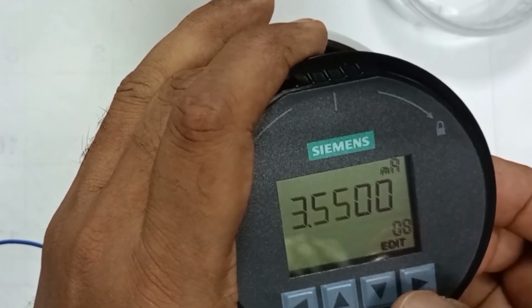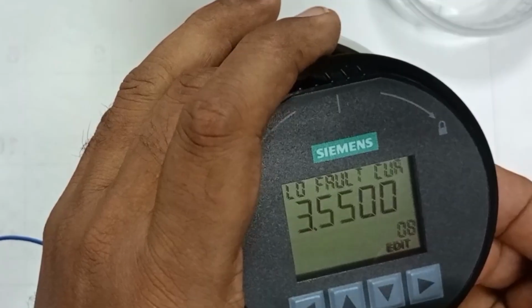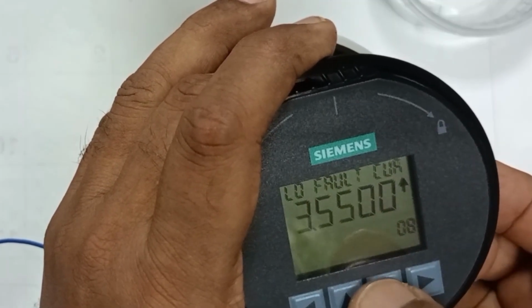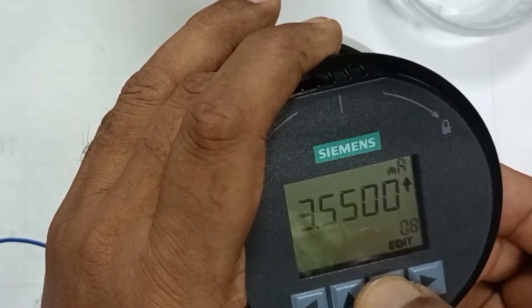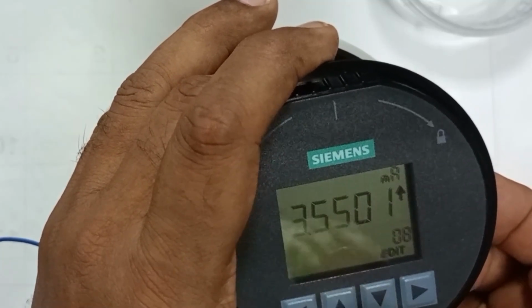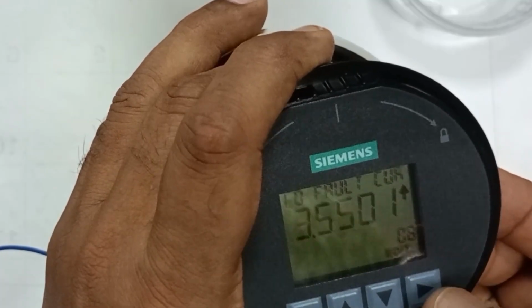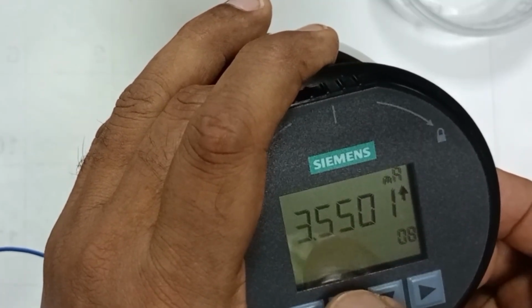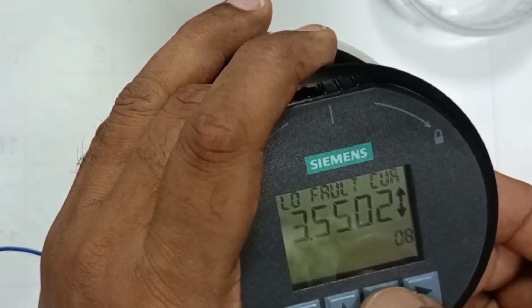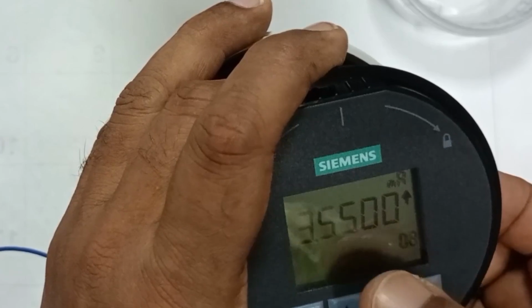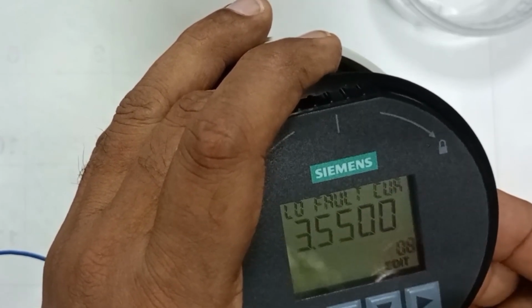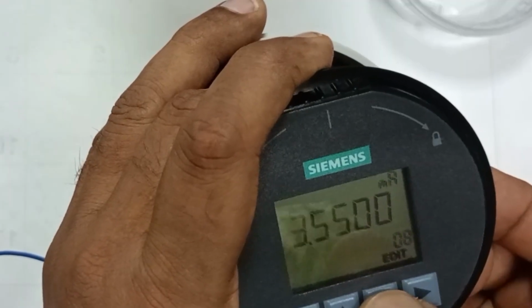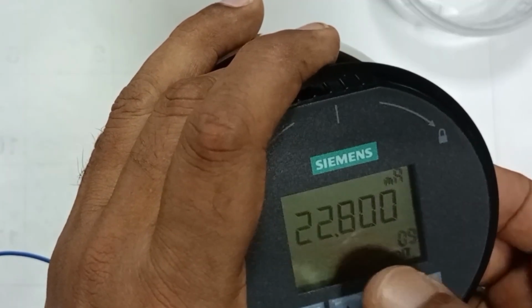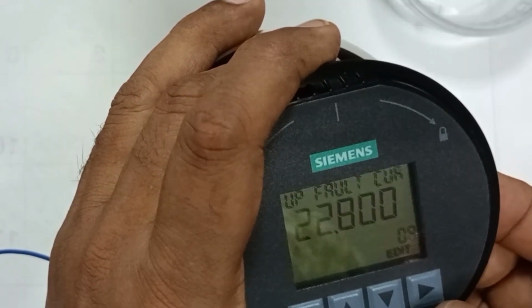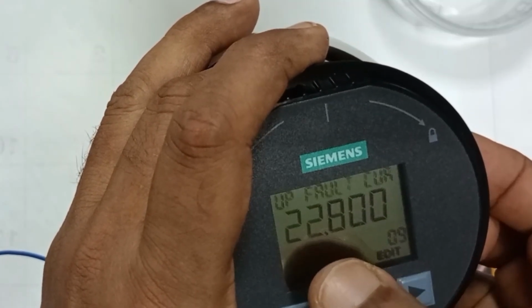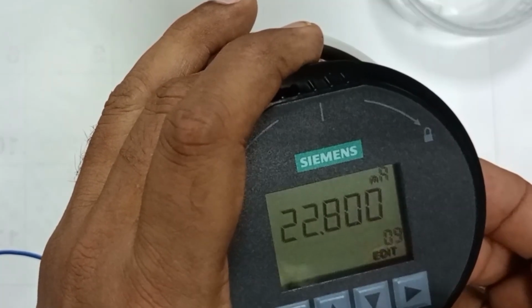You see low fault current 3.55. If you want to edit, we can set 3.5 or anything. The minimum level is 3.55. Okay, we'll set this. Now upper fault current is 22.8 milliampere. If the current exceeds 22.8 milliampere, then it will show fault.